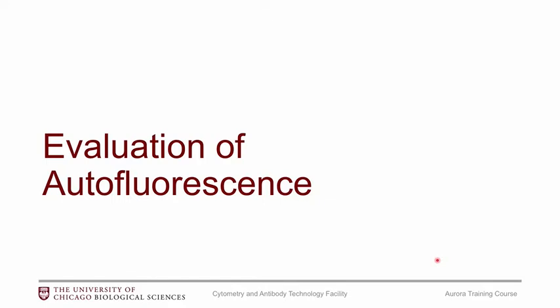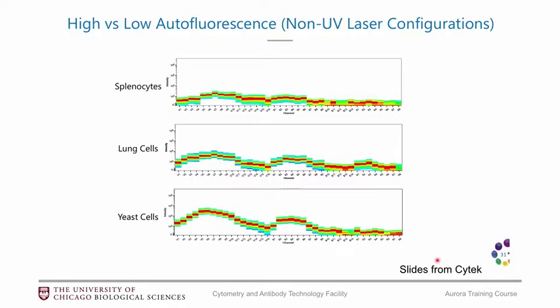One of the cool features of the Aurora is that you can extract the autofluorescence, which will improve your data. Here are some examples of autofluorescence using unstained cells run on the instrument. Splenocytes don't have a lot of autofluorescence, lung cells have a fair amount, and yeast cells have a pretty high amount. With the autofluorescence extraction, it will utilize this signature as a unique signature and put it into an additional channel in your unmixed file labeled AF.